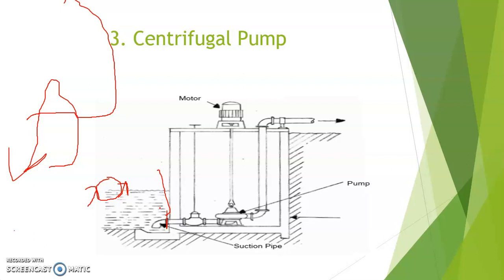Another thing is that in a centrifugal pump, there is a requirement of water always in the pump. Otherwise, air will entrain into this pump. And in order to remove that air from the pump, we need to add additional water from outside, which process is called priming. So in order to avoid air entrainment and backflow of water, we apply this foot valve.